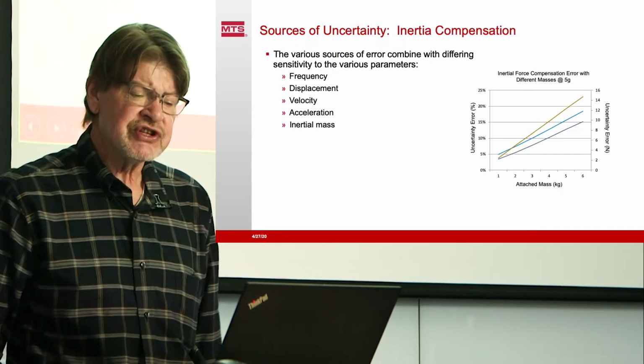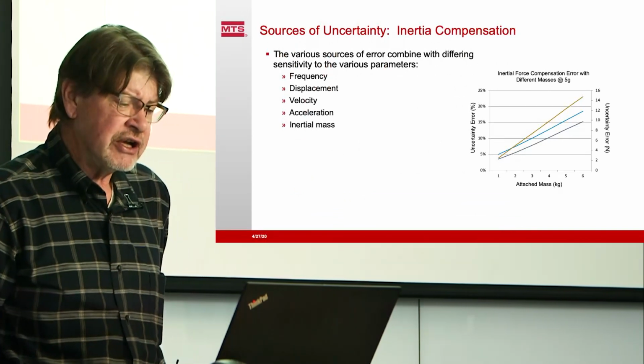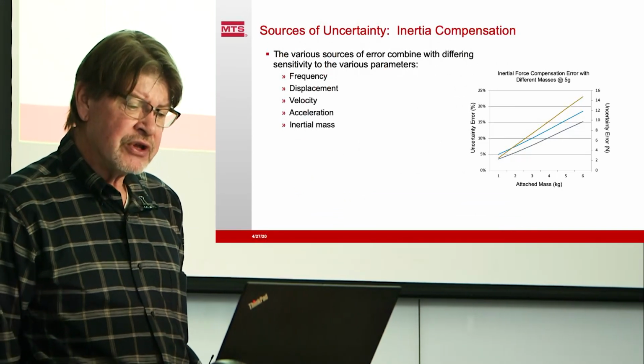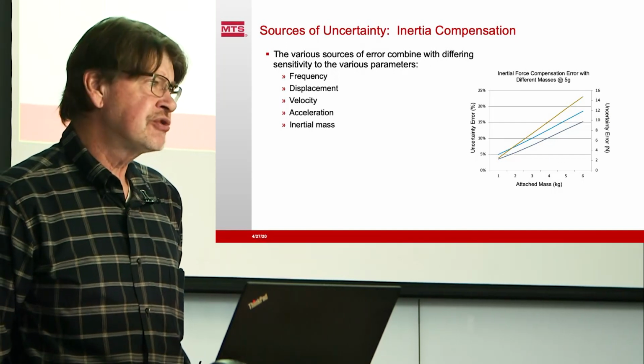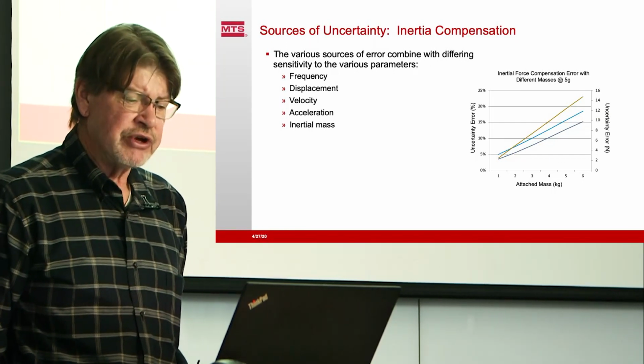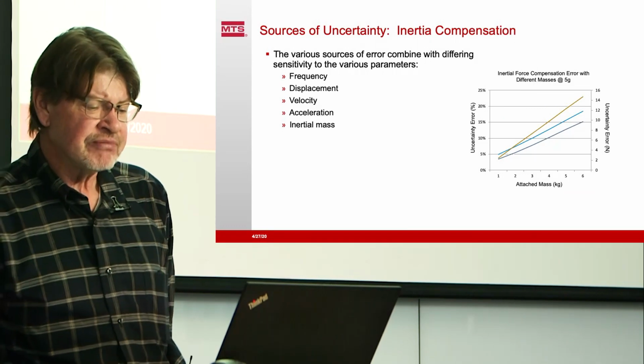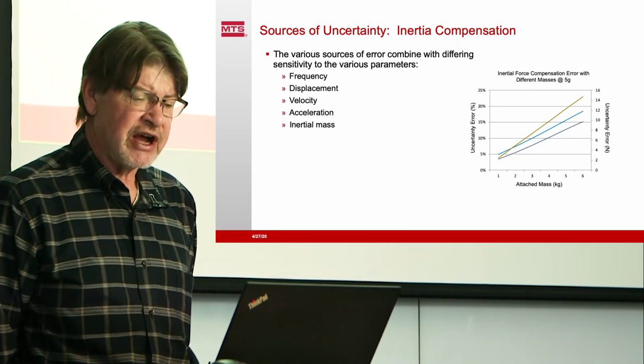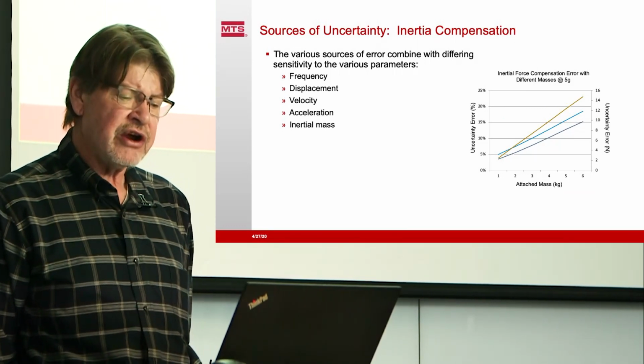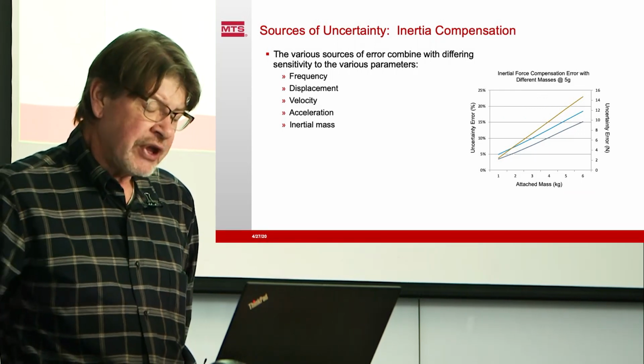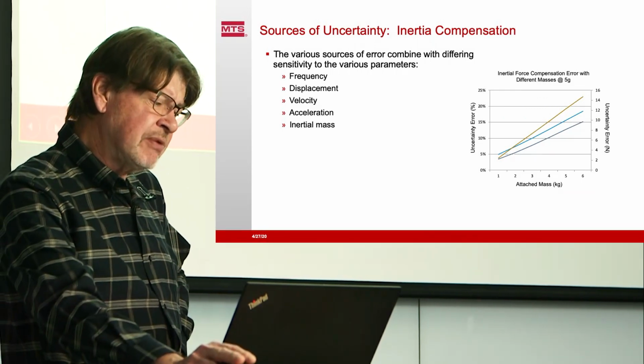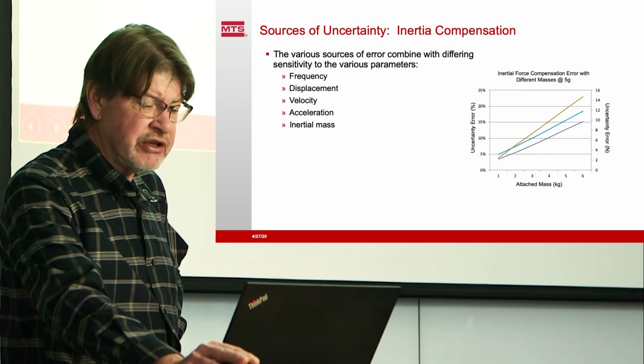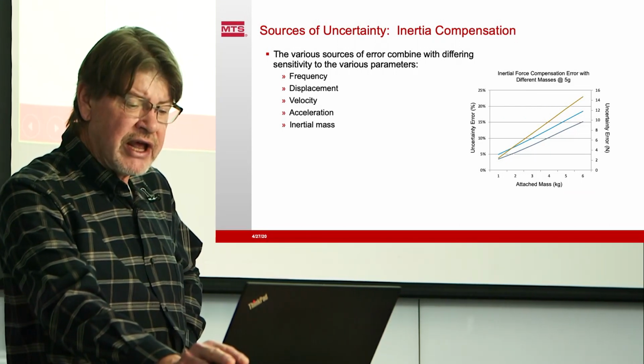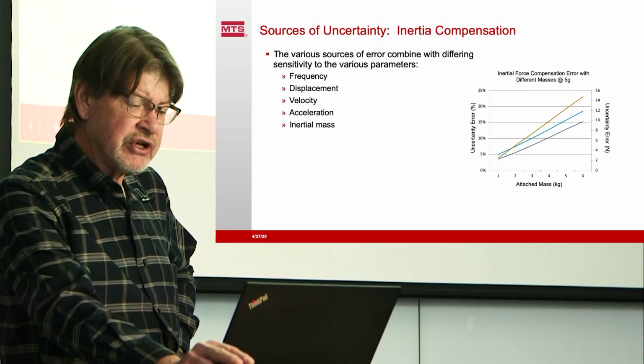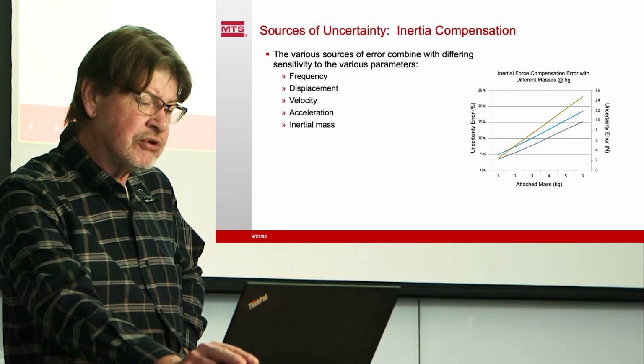Here's an example of investigating the uncertainty of an inertially compensated system. This was just a few simple tests that were run to demonstrate this. We had several different masses with a constant acceleration of 5 g's, and we looked at the uncertainty error of the correction. Variables include frequency, displacement, velocity, acceleration, and the mass. Those variables all add up to a fairly high level of uncertainty, as much as 25% in this example. Those numbers can be all over the map.